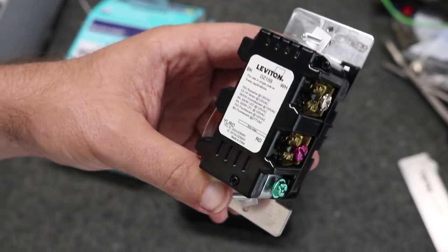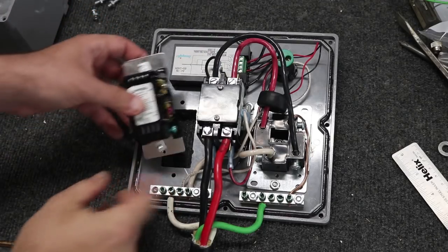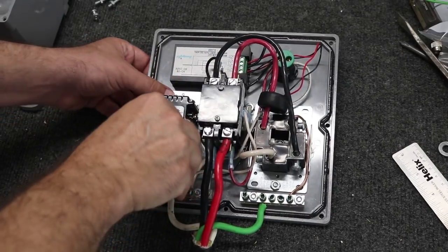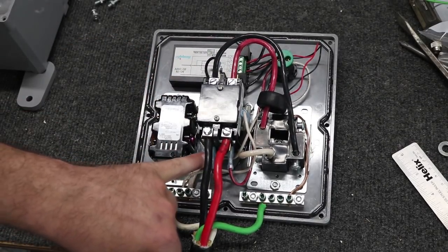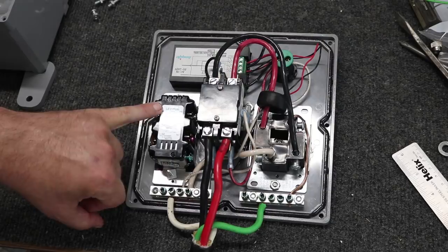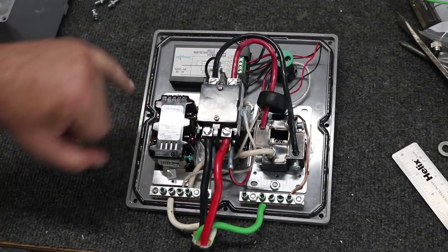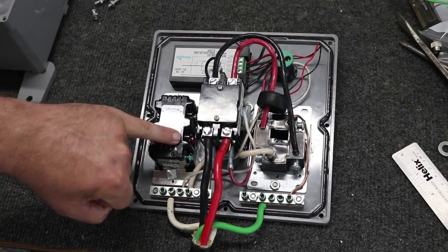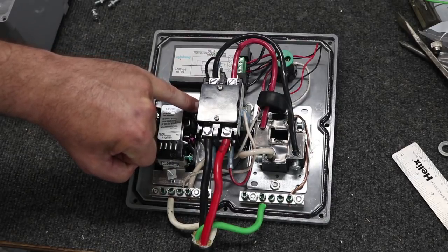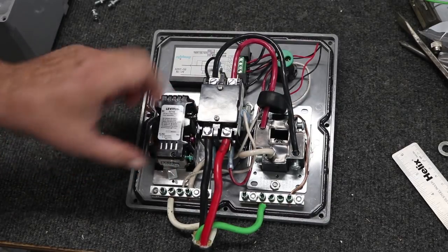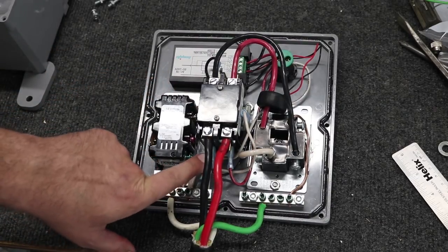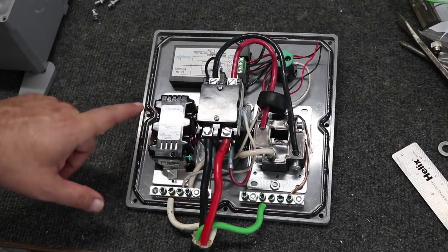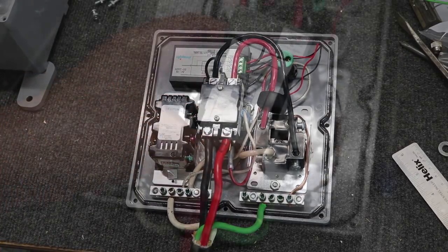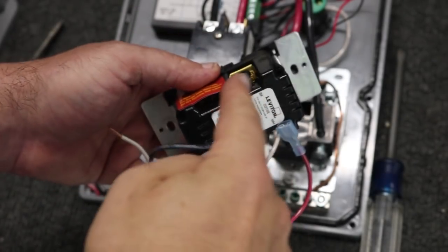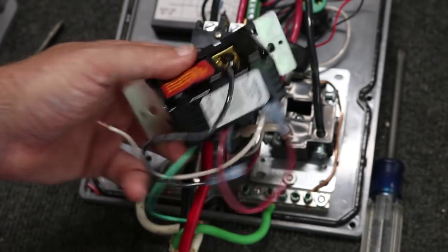Cool. So the switch is going to go right in this hole here, and what I need to do is connect hot to hot, neutral to neutral, and then that red switched hot output is going to go to the coil here, and then 2 screws to mount it down into place. So I'll use some spade connectors onto a couple short pieces of wire. I just added the short wires to the back of the switch.